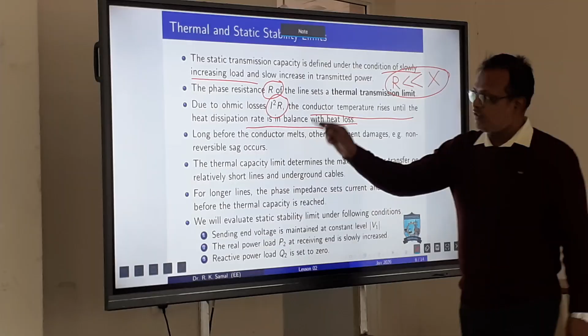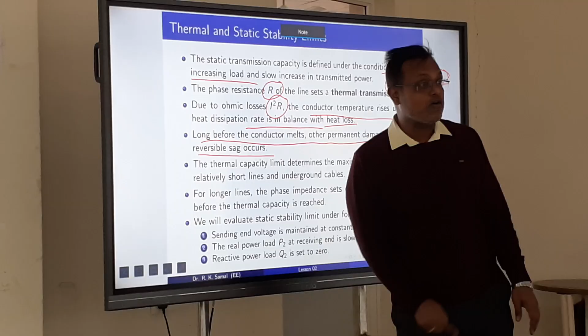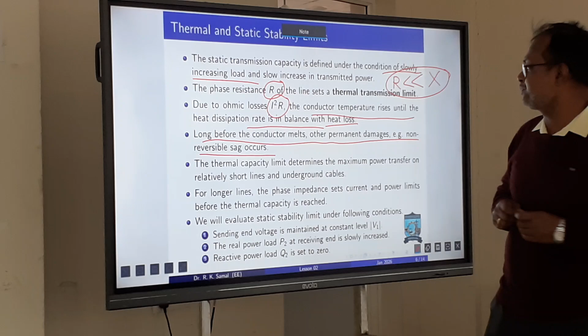Okay, the conductor temperature rises until the heat dissipation rate is in balance with the heat loss. See, long before the conductor melts, other permanent damages, that is non-reversible sag, occurs. Conductors never melt, it is very rare, but sag will be there, it will expand. Okay. The thermal capacity limit determines this, you write this one.